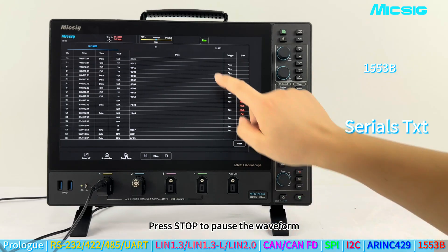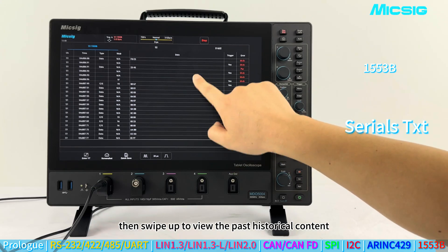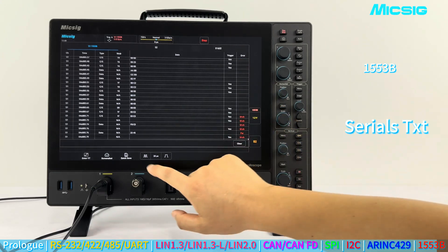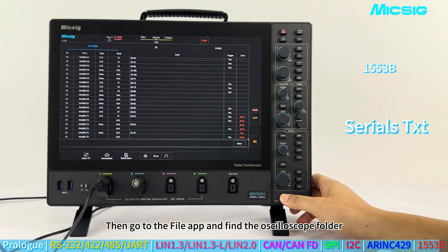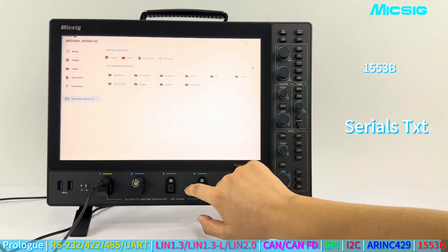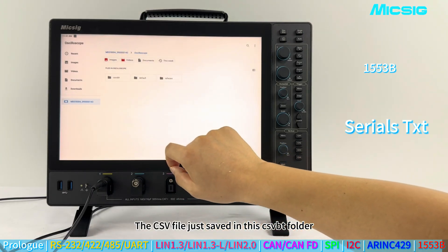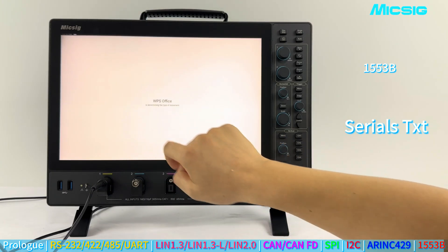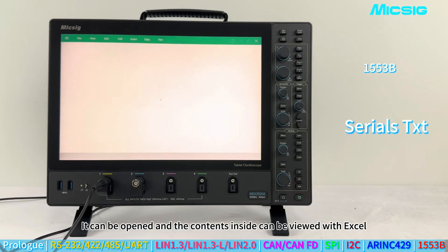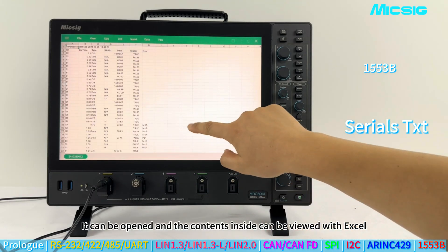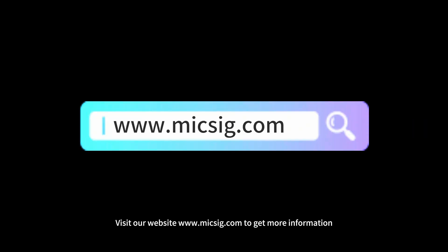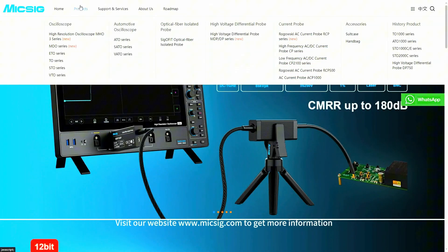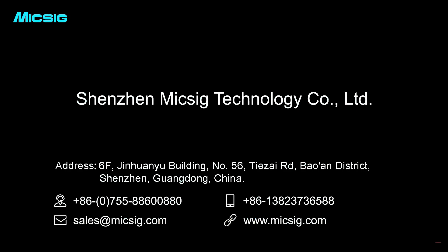Press stop to pause the waveform, then swipe up to view past historical content. Click the Quick Save button to save in CSV format, then go to the file app and find the oscilloscope folder. The CSV file is saved in the CSVBT folder and can be opened and viewed with Excel. Visit our website at www.micsig.com to get more information.